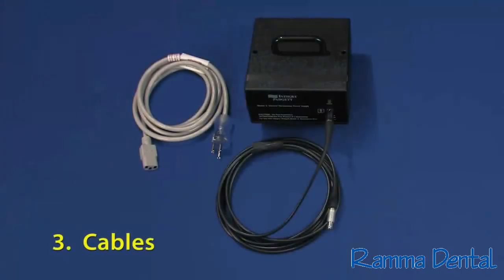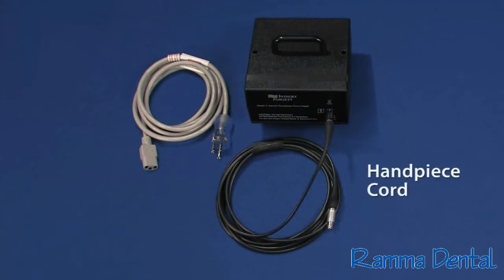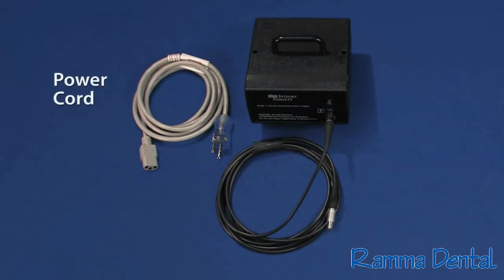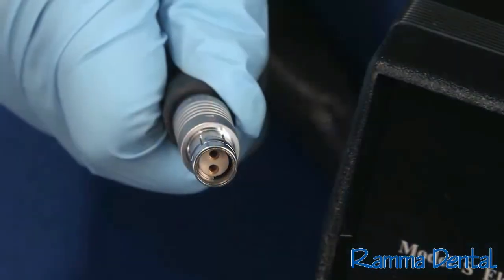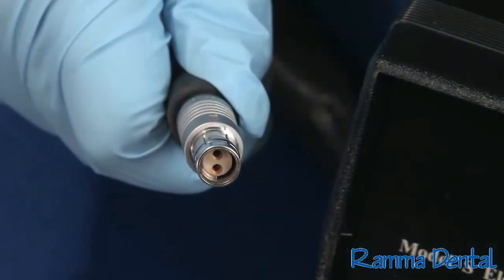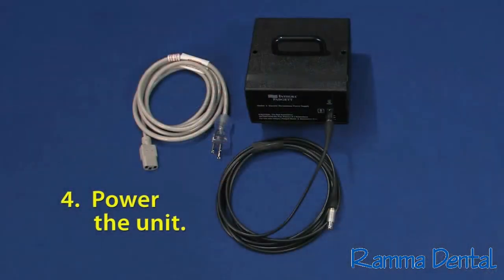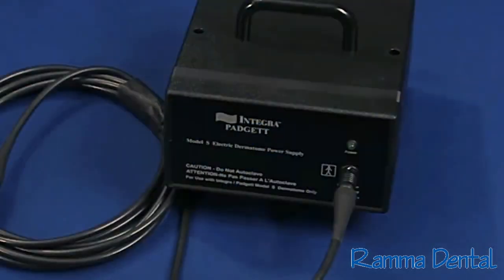3. Check for proper fit of all dermatome cables. Connect the dermatome handpiece cord between the dermatome handpiece and the power supply. Connect the wall power cord to the power supply. All cable connectors are to fit properly to their mating receptacles. 4. Connect the power supply cord to a wall receptacle and turn the power supply switch on. The indicator light on the power supply is to illuminate.